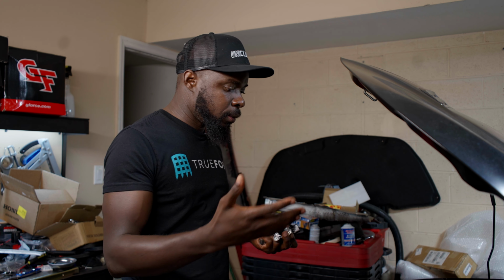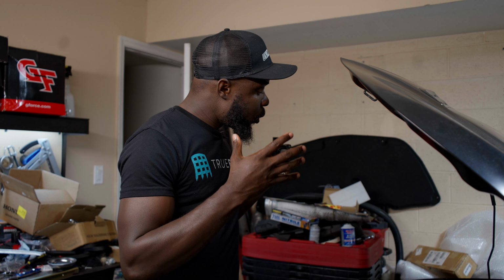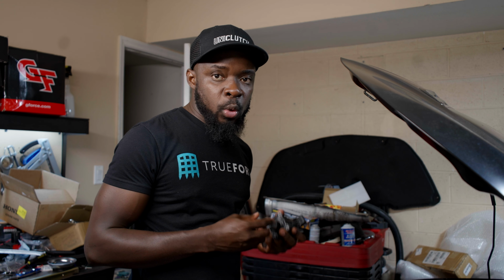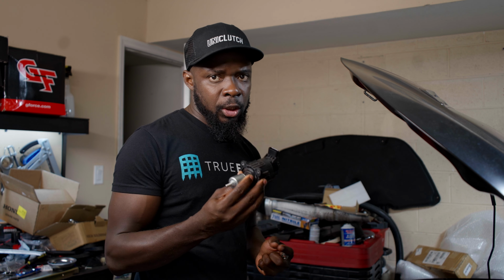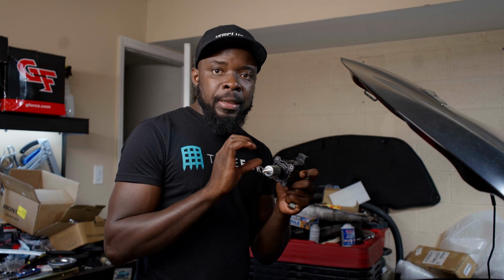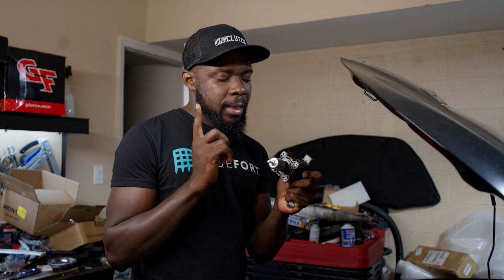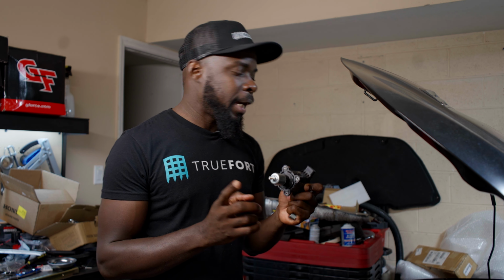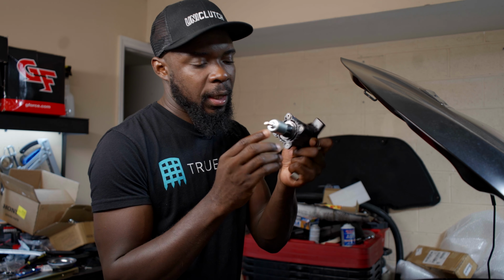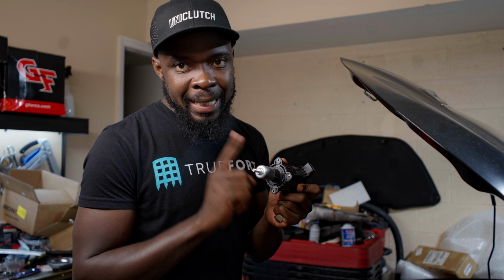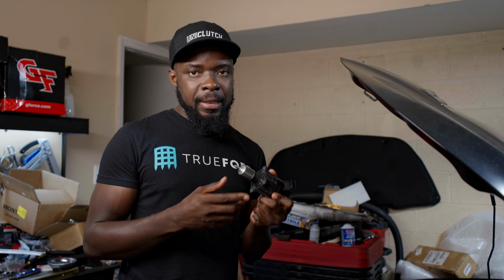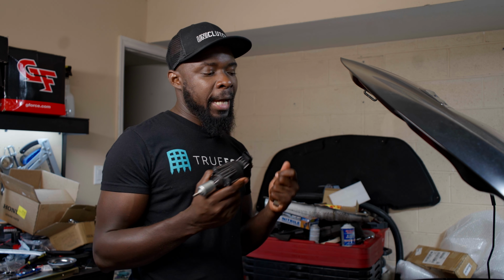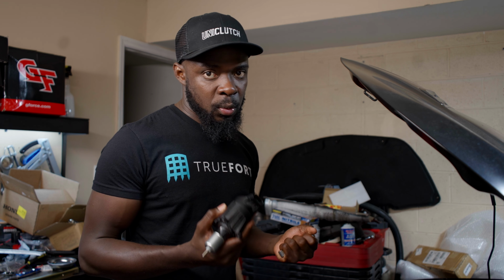When you get into your scanning tool, you will want to actuate this one using the scanning tool. When you are in the actuator function, set it into open and close, and you will see the movement, opening and closing, going back and forth. If you are not getting that, there are many things that could go wrong, and we are going to move to the next one.